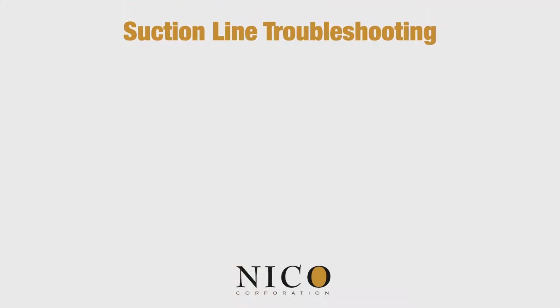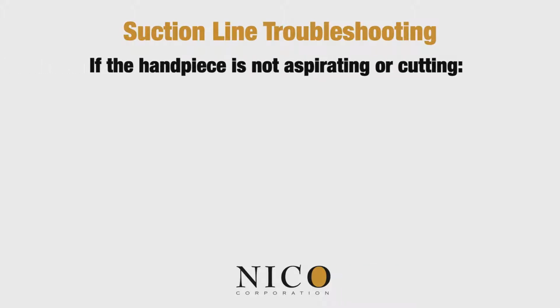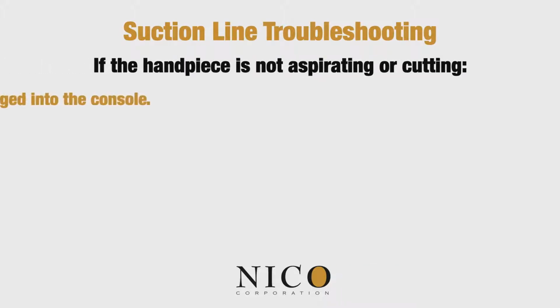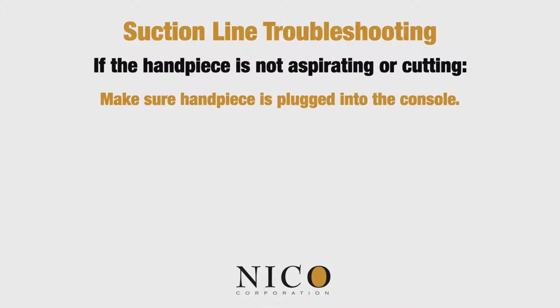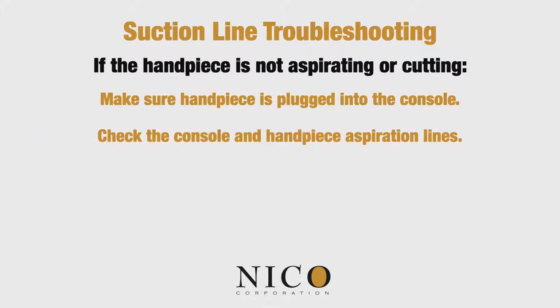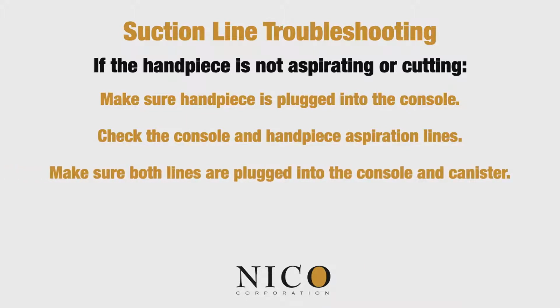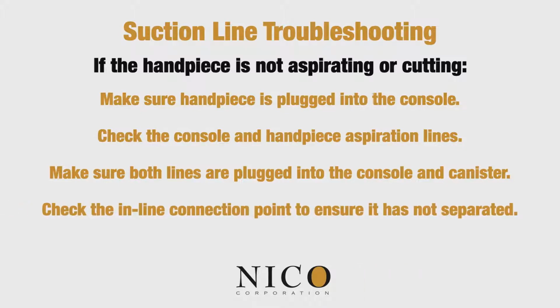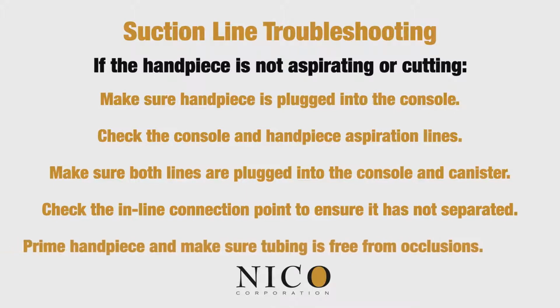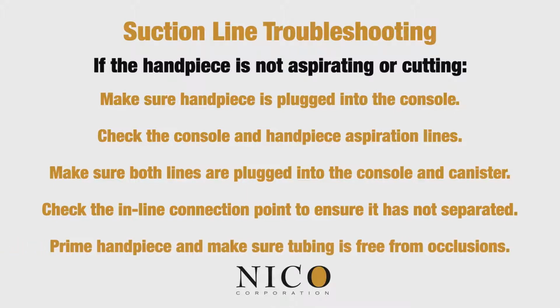Suction line troubleshooting. If the handpiece is not aspirating or cutting, make sure the handpiece is plugged into the console. Check the console and handpiece aspiration lines. Make sure both lines are plugged into the console and canister. Check the inline connection point to ensure it has not separated. Prime the handpiece and make sure tubing is free from occlusions.